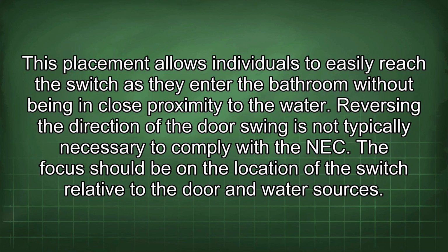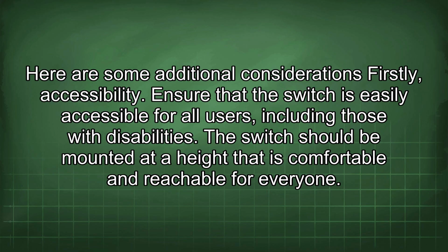This placement allows individuals to easily reach the switch as they enter the bathroom without being in close proximity to the water. Reversing the direction of the door swing is not typically necessary to comply with the NEC. The focus should be on the location of the switch relative to the door and water sources. Here are some additional considerations.